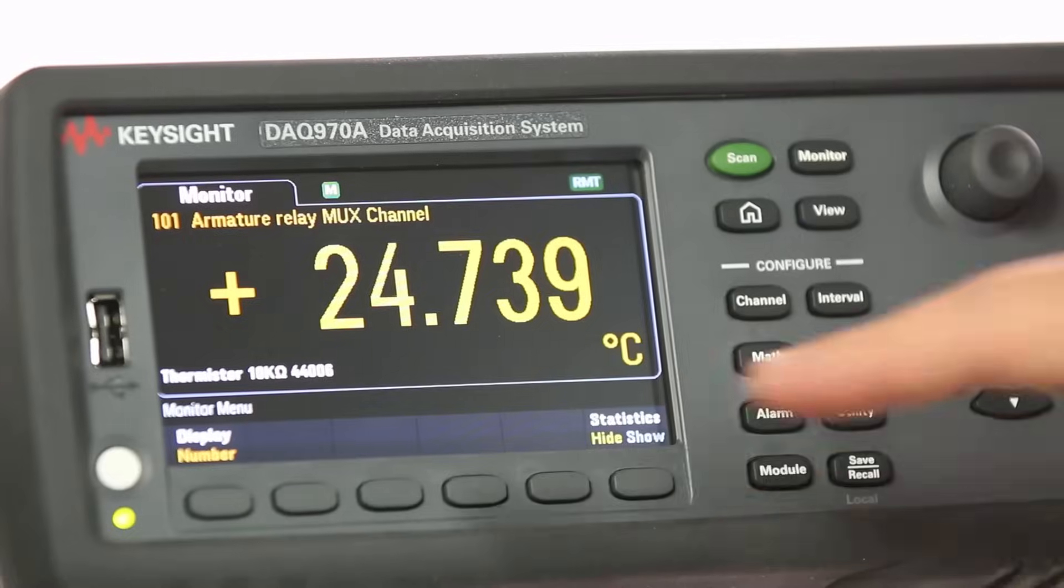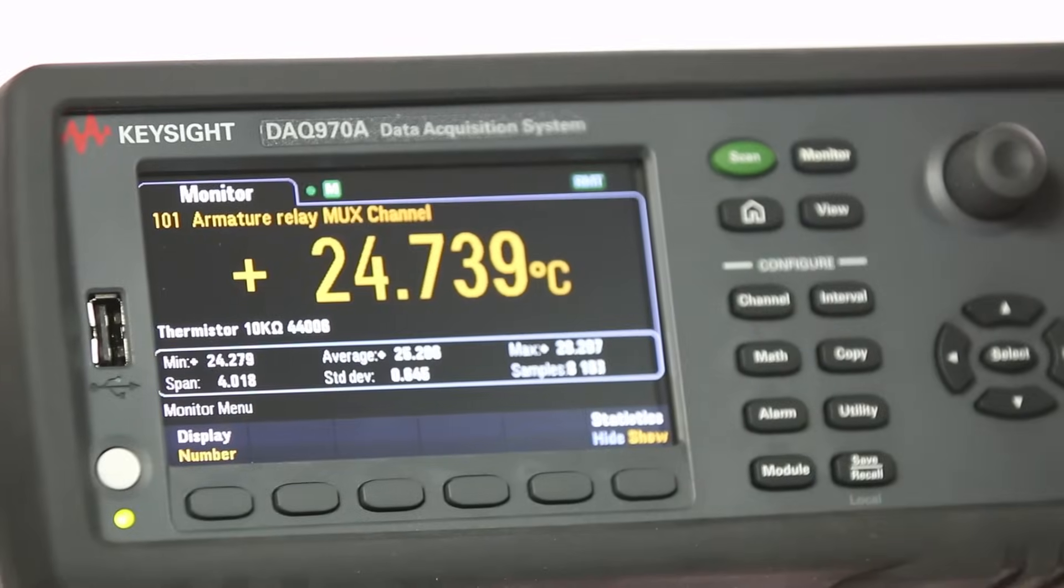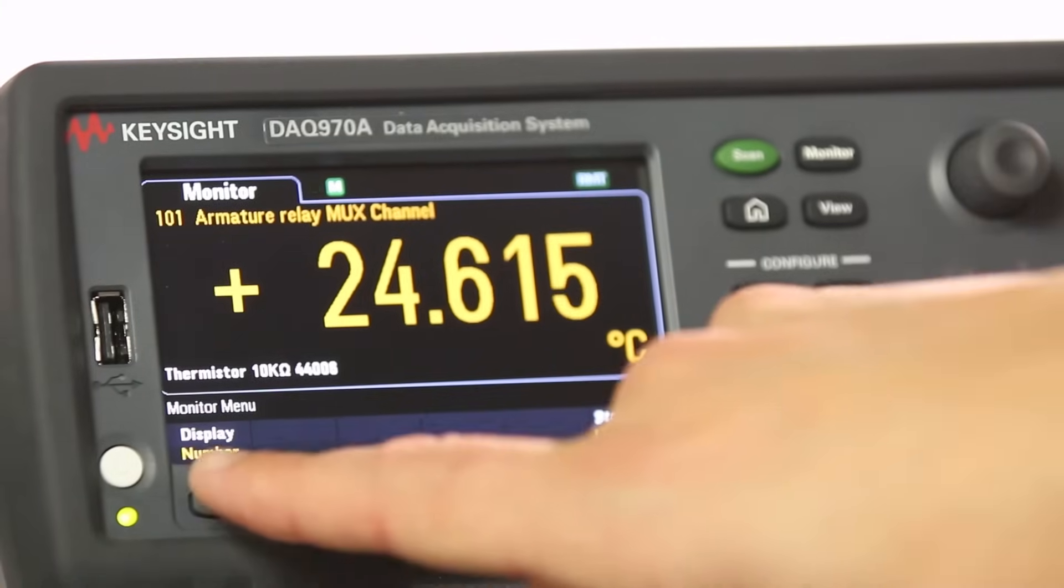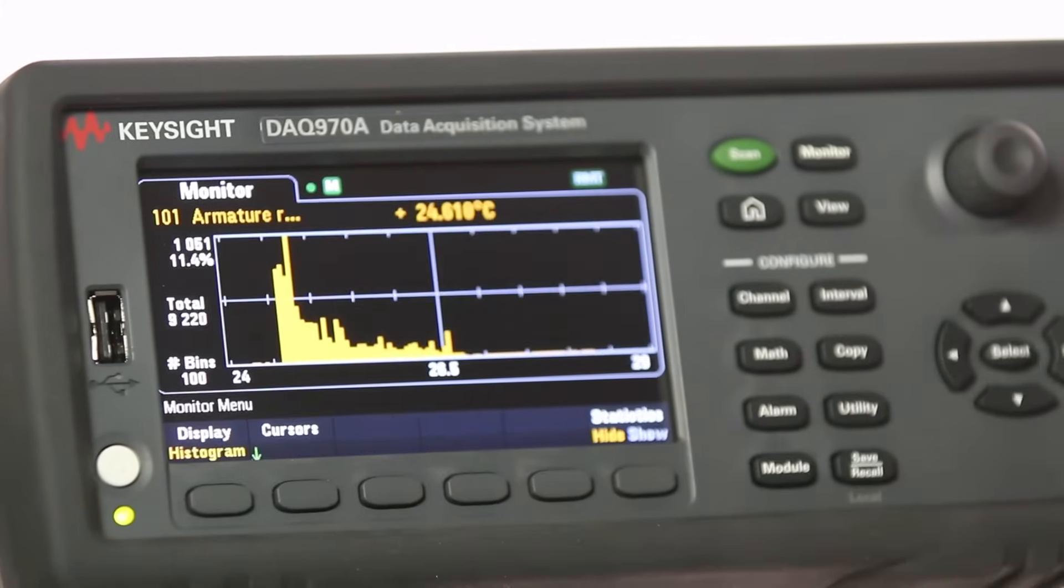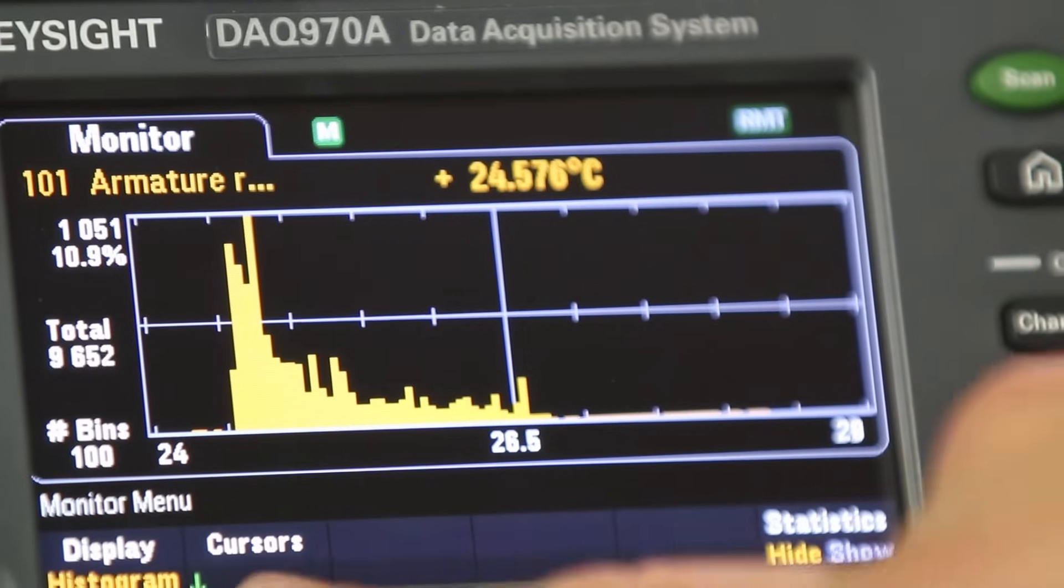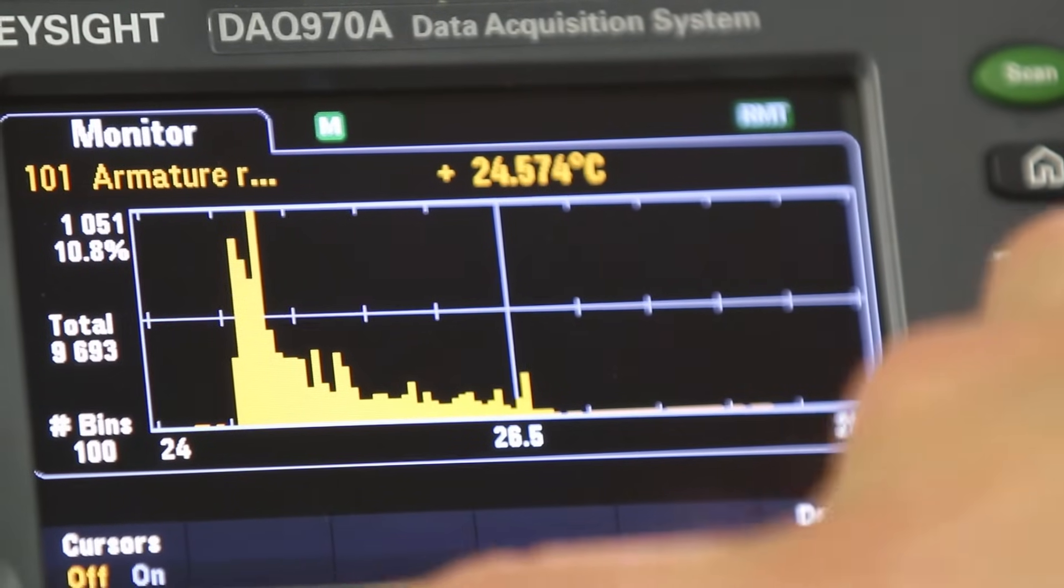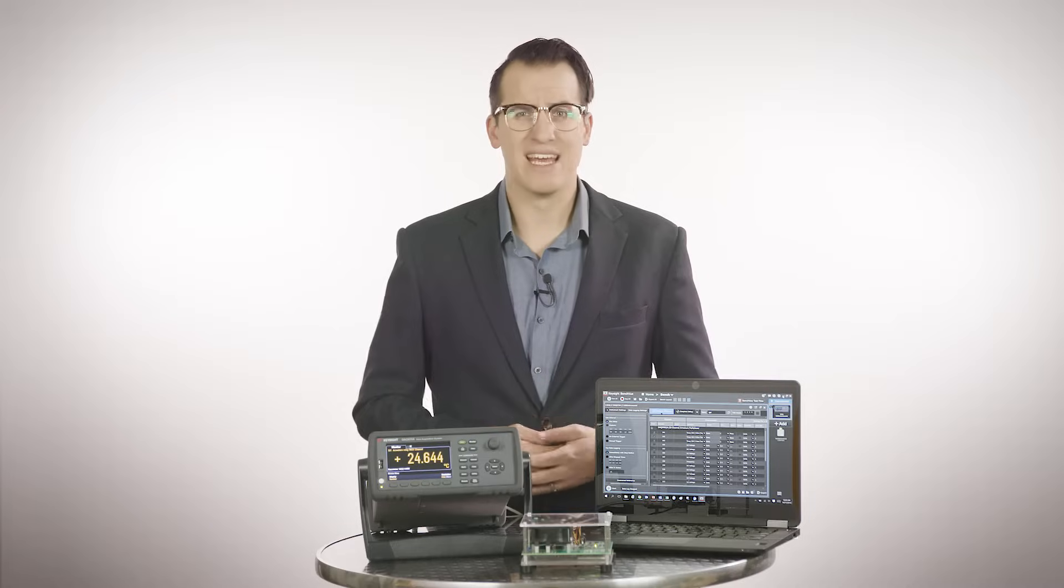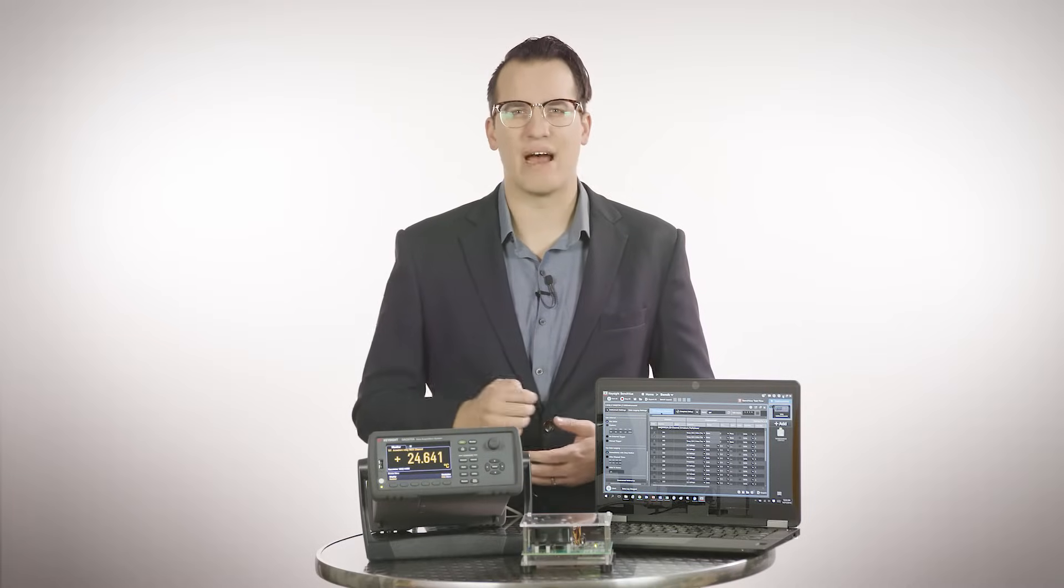It also has expanded measurement types and ranges. On top of the 11 measurement types that the previous generation could measure, the DAQ 970A can measure diodes and capacitors. And it can measure very low current ranges, 1 microamp DC and 100 microamps AC, and it has a higher resistance range of 1,000 megaohms.